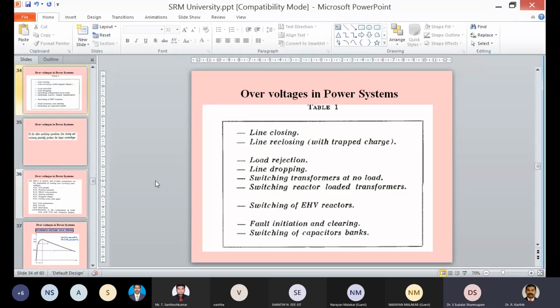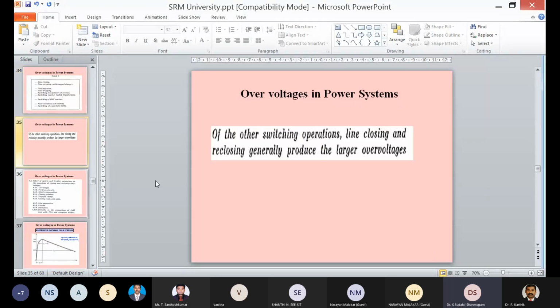Your switching fault might be caused because of line closing, load rejection, a line dropping. That is one of the worst faults, of course. Irrelevant closing of your circuit breakers, that is non-synchronous motion of the circuit breaker terminals. And the switching transient will be very severe in two conditions. One is during the opening and another one is closing.